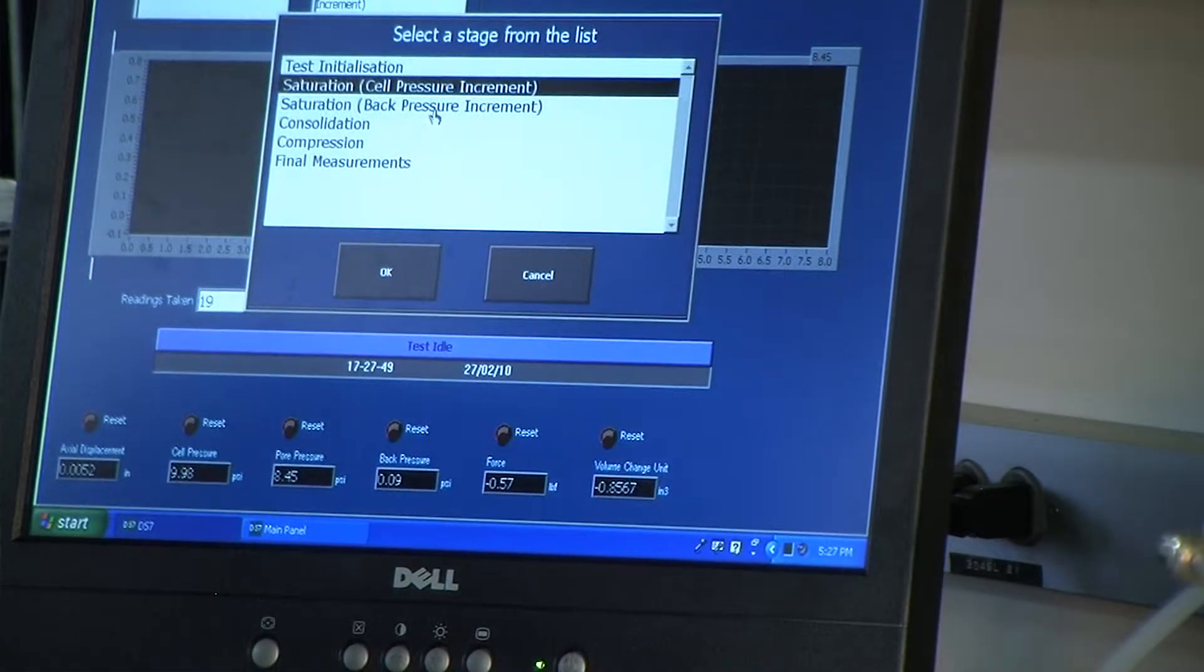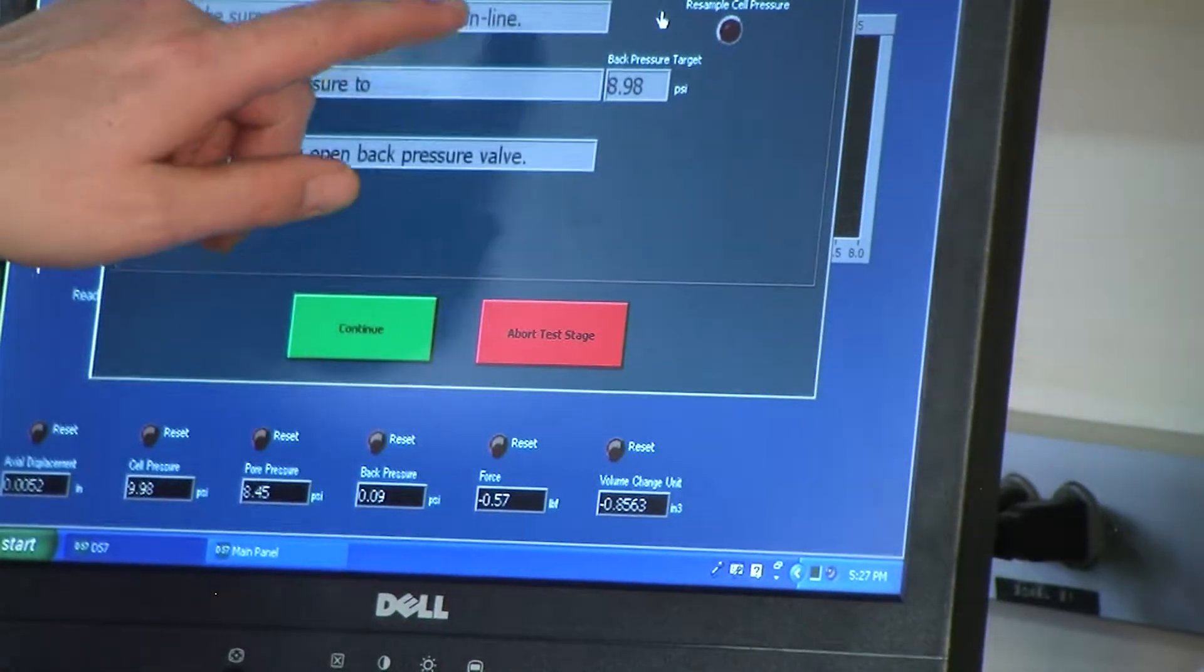We're going to go to saturation, backpressure increment, click okay, and again, follow the instructions on the screen. Step 1, make sure the volume change unit is online.